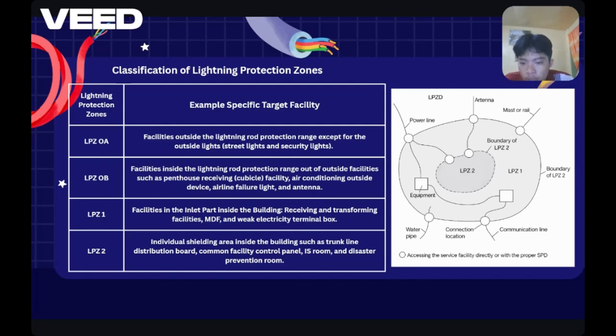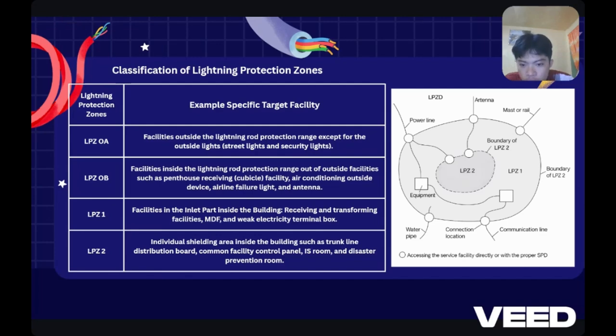LPZ 0A is the facilities outside the lightning rod protection's range, except for the outside lights, street lights, and security lights. And LPZ 0B is the facility inside the lightning rod protection range out of the outside facilities, such as penthouse receiving facility, air conditioning outside devices, airline failure light, and antenna.